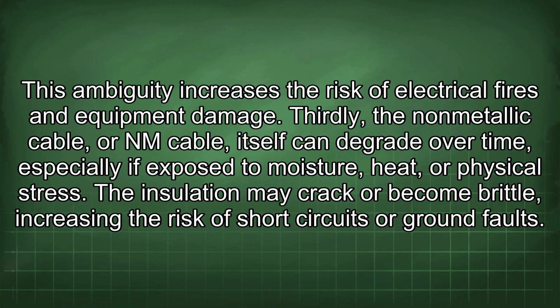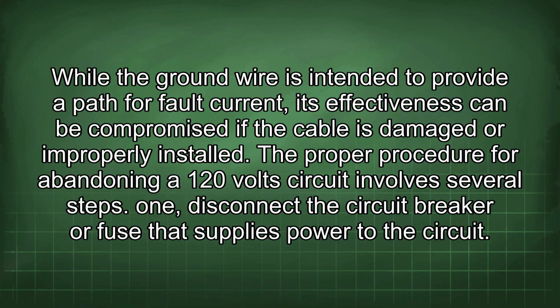Thirdly, the nonmetallic cable, or NM cable, itself can degrade over time, especially if exposed to moisture, heat, or physical stress. The insulation may crack or become brittle, increasing the risk of short circuits or ground faults. While the ground wire is intended to provide a path for fault current, its effectiveness can be compromised if the cable is damaged or improperly installed.